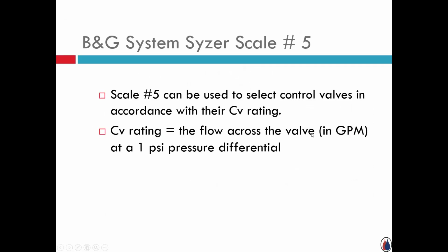One last thing on scale 5. It can be used to select control valves. And what we're saying here is manufacturers, when they manufacture their valves, there's an orifice. And it could be a fluctuating orifice. It could be different ports, full port, reduced port, standard port, et cetera. But they have a rating. And they rate it in this thing called a CV, C sub V rating.